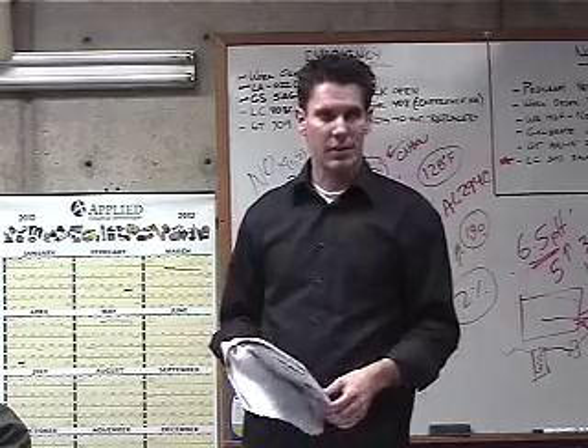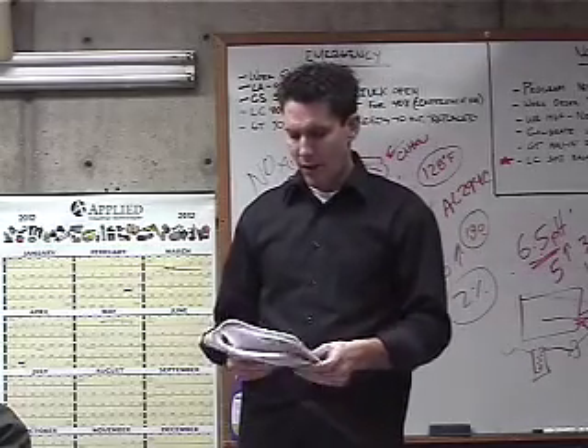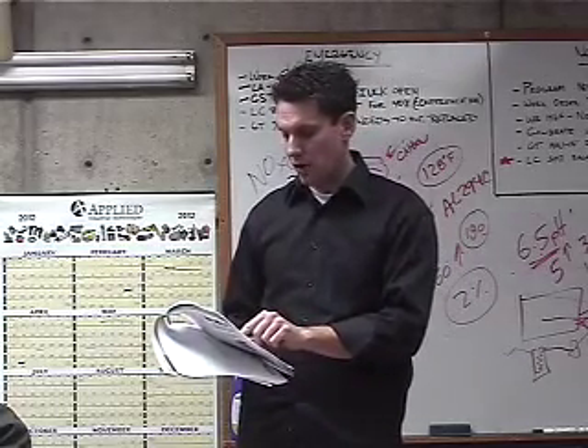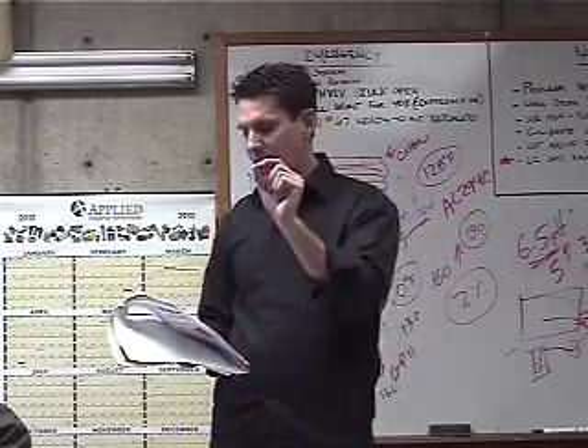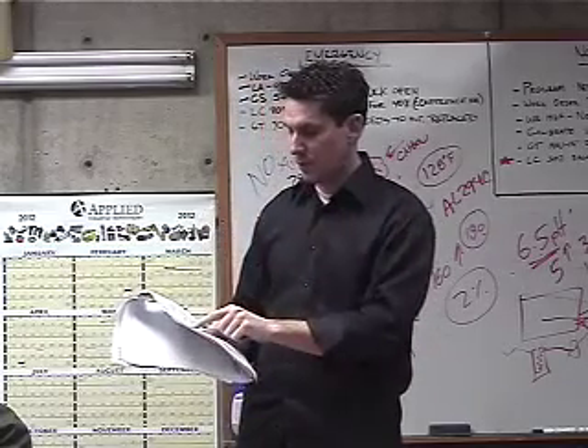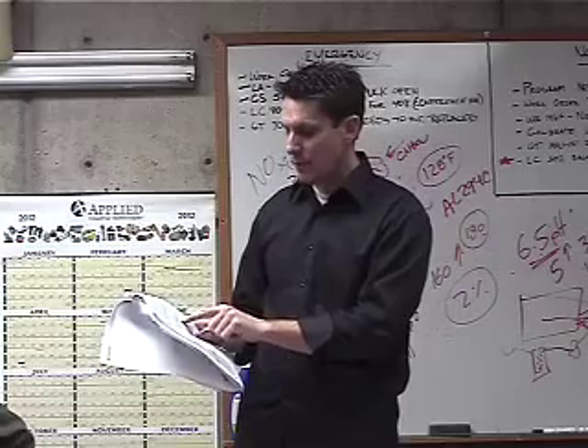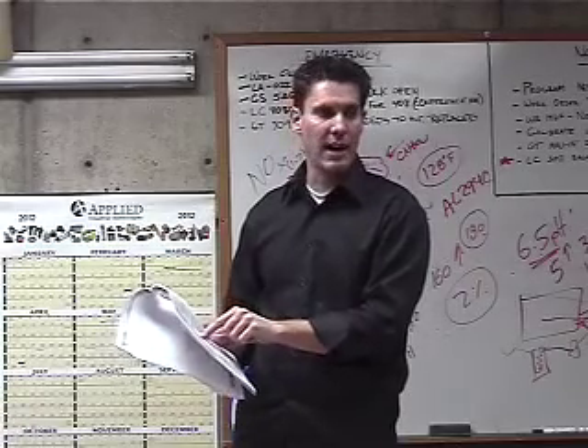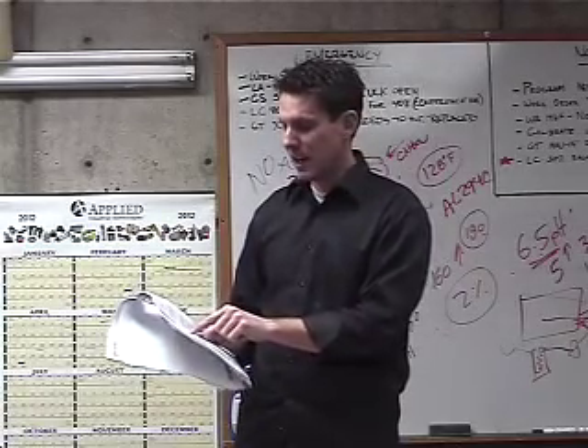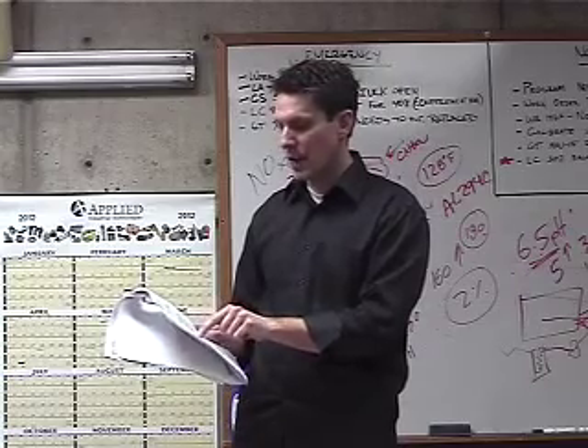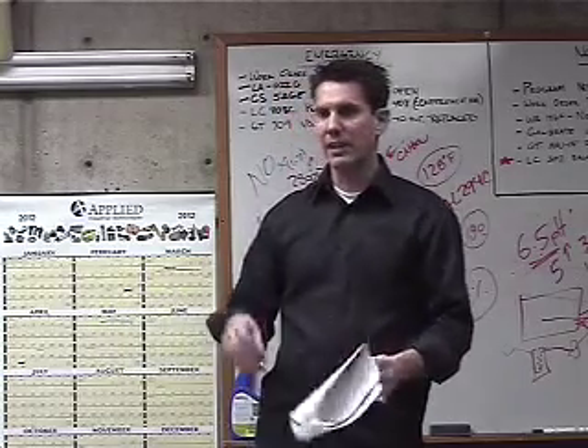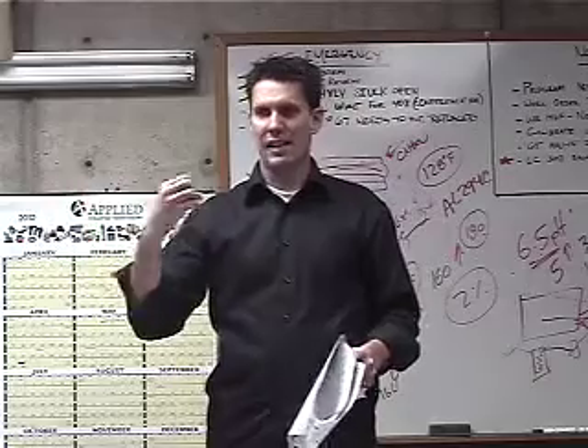And then the last, make sure that the clearance area around the boiler is free of combustibles, just safety-wise. On a weekly basis, look in and make sure of the flame, this is where it gets important. A normal high fire flame shows an orange screen with a blue halo. That's what you should see. In low fire, the burner should display a reddish orange glow. If you ever see the flame leaping, what is that a sign of?